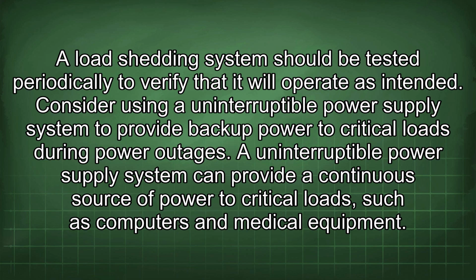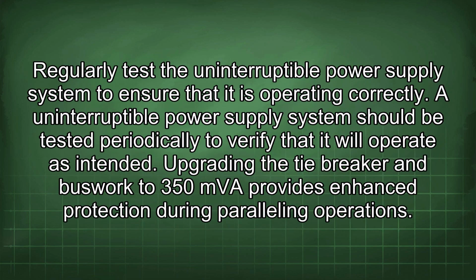Consider using an uninterruptible power supply system to provide backup power to critical loads during power outages. An uninterruptible power supply system can provide a continuous source of power to critical loads such as computers and medical equipment. Regularly test the uninterruptible power supply system to ensure that it is operating correctly. An uninterruptible power supply system should be tested periodically to verify that it will operate as intended.